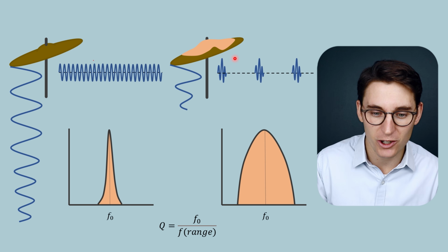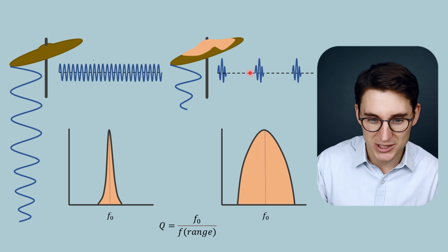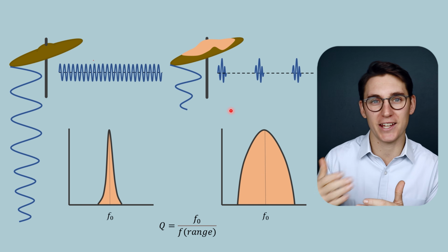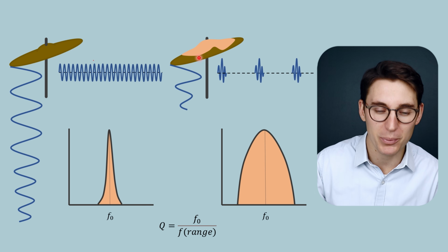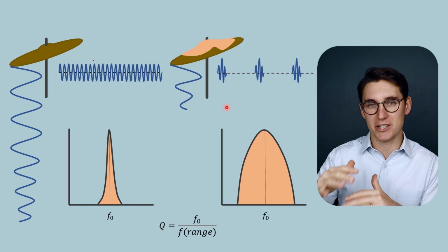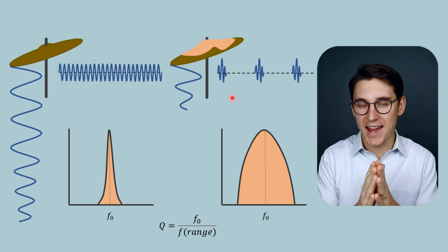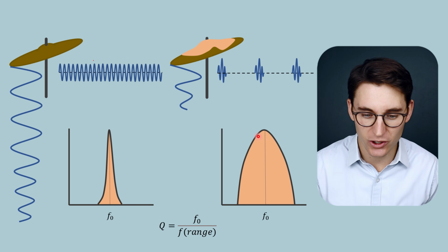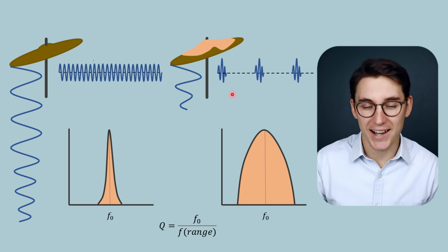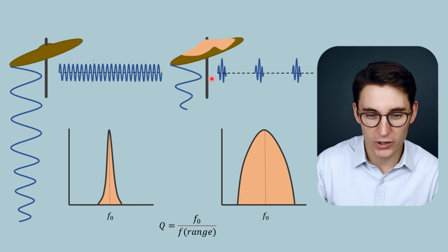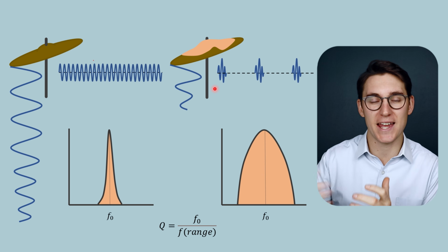Now, when we looked at pulse echo ultrasonography, we saw that we needed to reduce that spatial pulse length in order to have this receive time, in order to register the returning echoes and plot them at a distance away from our ultrasound transducer. And we did this by dampening the piezoelectric material. That dampening material is much like a wet rag on top of this cymbal. It makes that note when we hit the cymbal short and have quite a wide range of frequencies. It's got a wide bandwidth, a low quality factor. But that wide bandwidth allowed us to have a short spatial pulse length, a really short, sharp pulse that went into the tissues, and then we could spend the rest of the time waiting for those echoes to return.